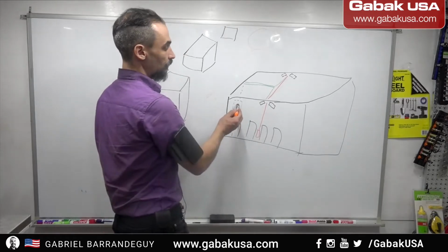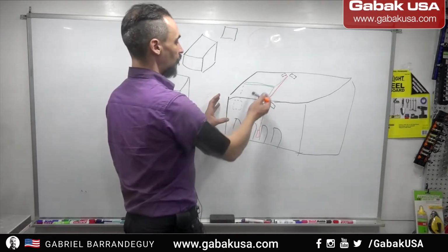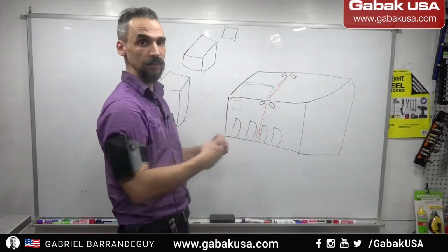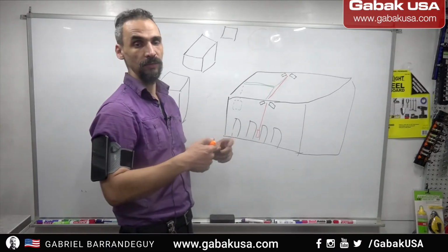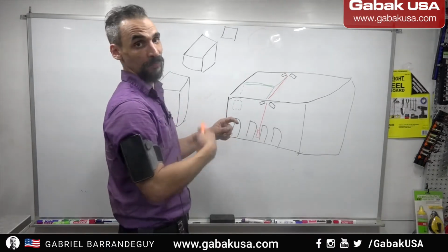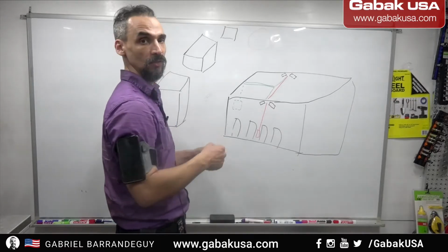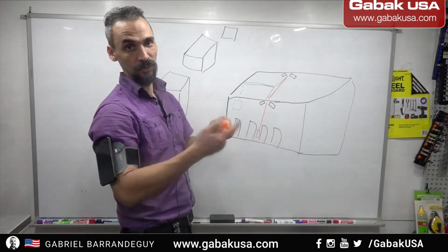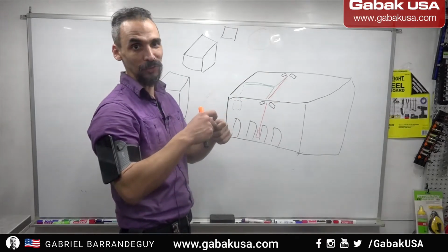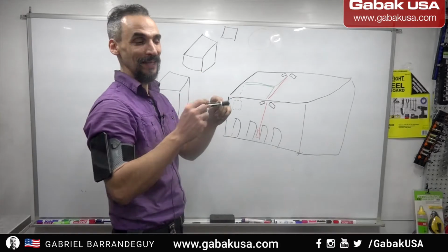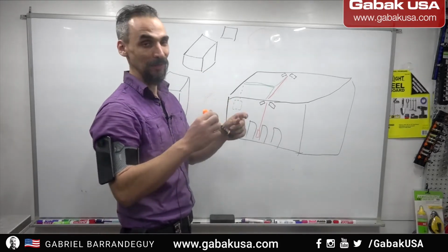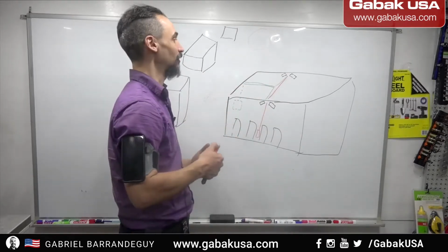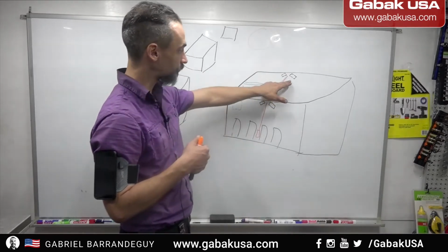And I went here. Here is the junction box. Here is where you have all the connections together in one place. So I went here, I tested, and things were not working or were kind of intermittent. So what I did is I re-terminated those connectors as well, and then things started working. But I also saw that the power cable was all cracked, and the cable was kind of white, and it was red in the beginning. All because the sun fades out all the colors and everything.